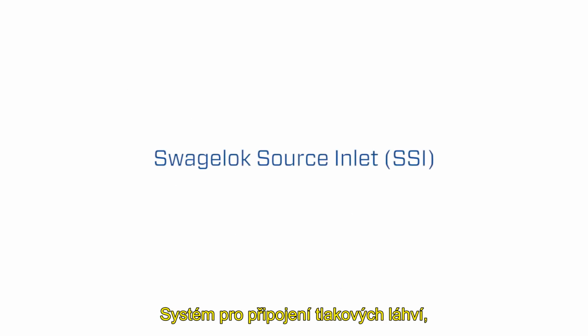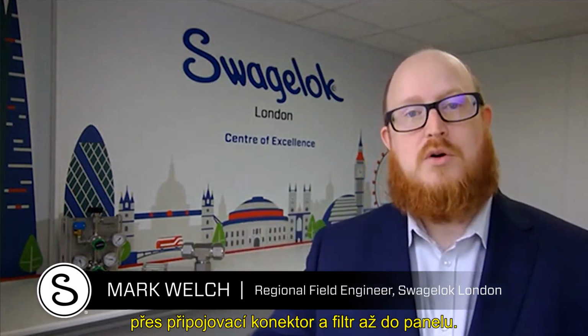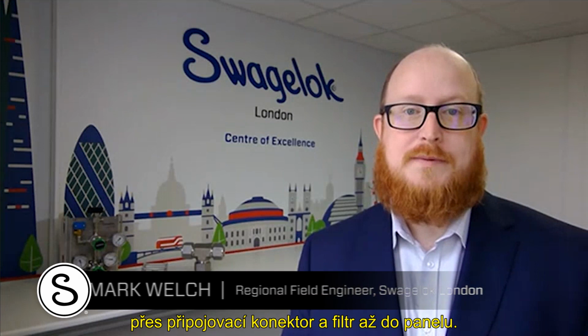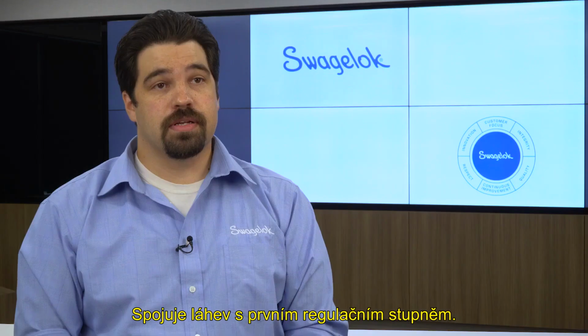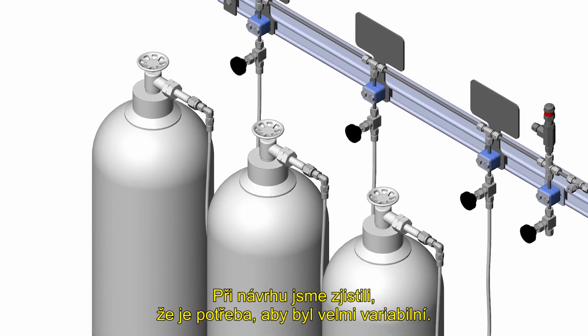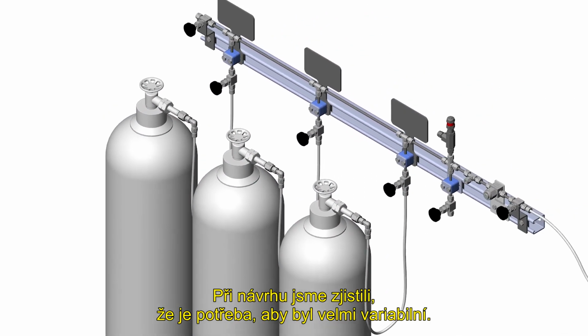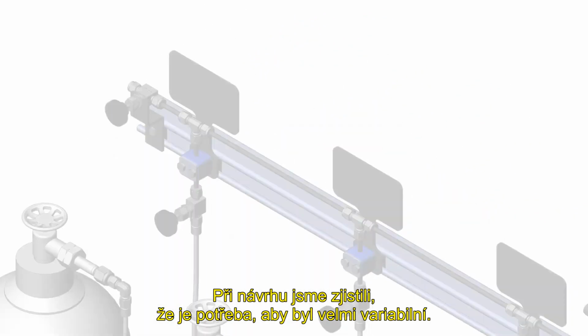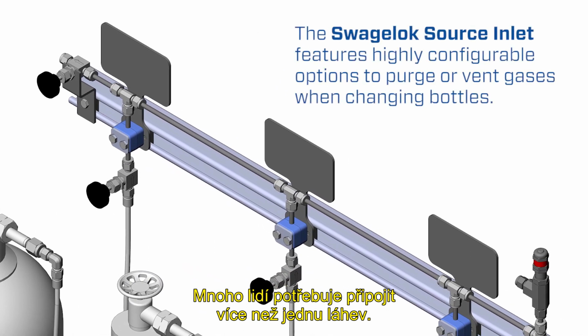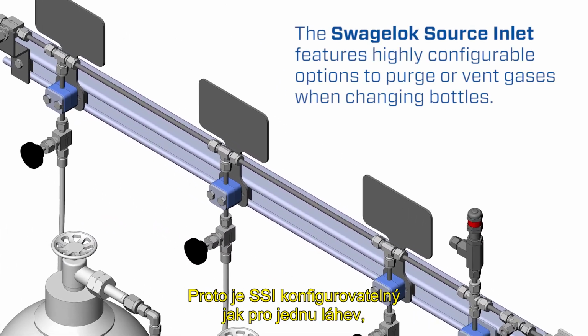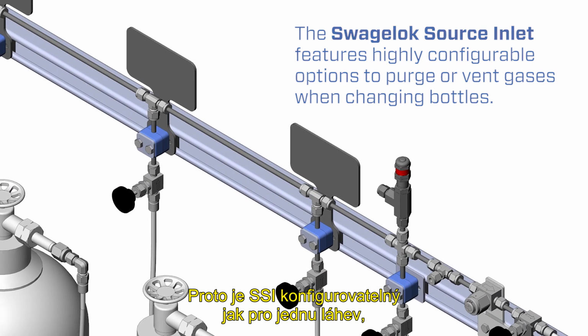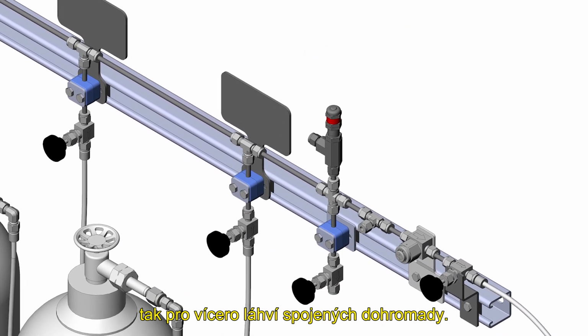The SSI is the Swagelok source inlet. It's designed to take pressure from the gas bottle through a bottle connector, through a filter, and then into the panel. It connects the bottle to the first stage of regulation. And as we were engineering it, we discovered that there was a need to have a lot of variation in it. A lot of folks need to connect more than just one bottle at a time, and so it's configurable from just supplying gas from one bottle to many bottles manifolded together.